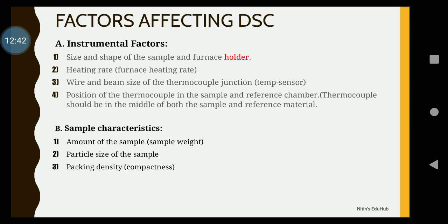Then the position of the thermocouple in the sample and the reference chamber. We have also discussed this in the case of DTA. There are three positions: either near the sample holder, in the sample holder, or in the sample. These are the three positions mostly preferred, on the basis of the material used in the sample holder as well as the material of the thermocouple and their compatibility.